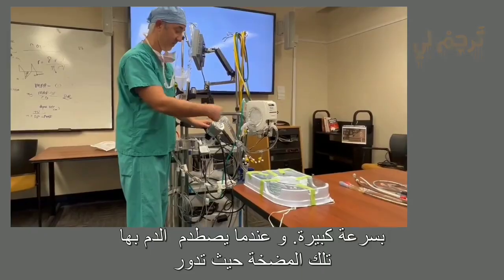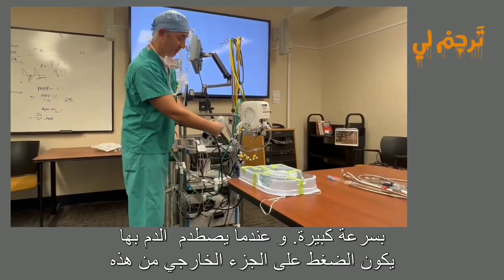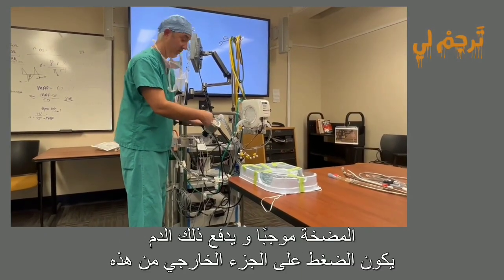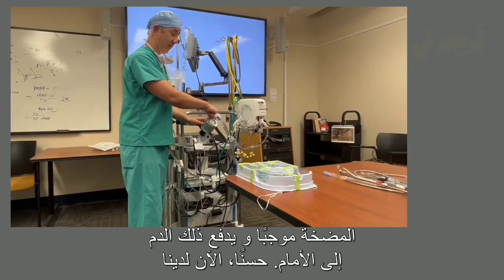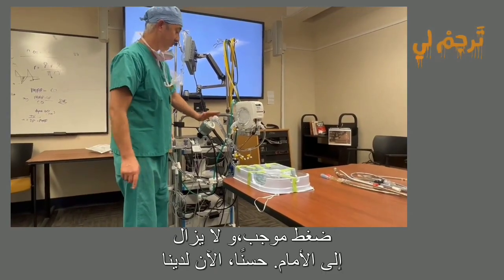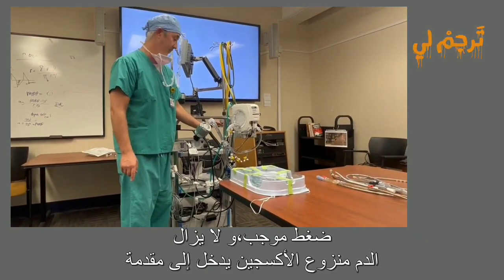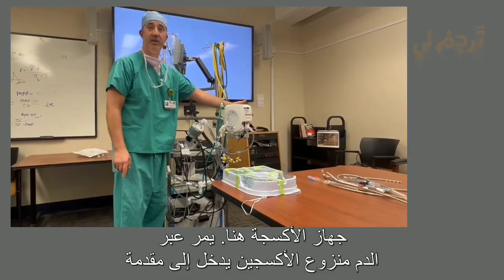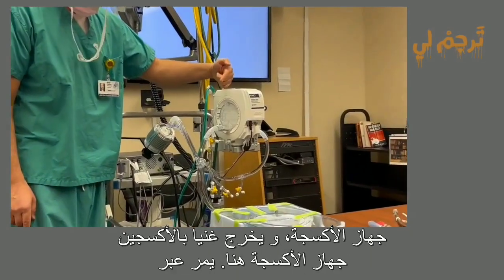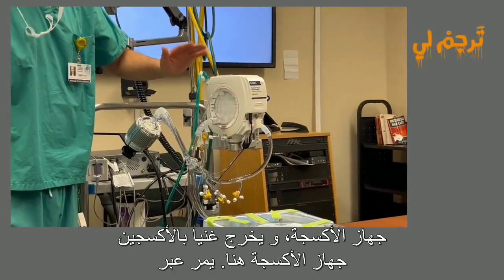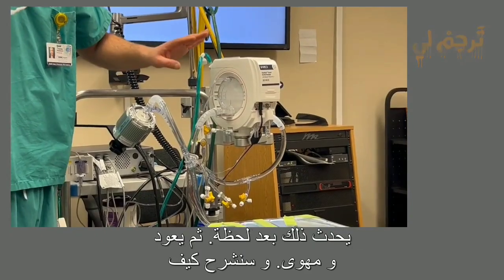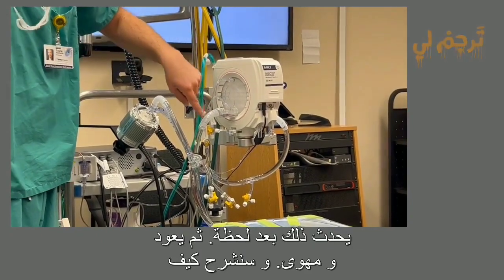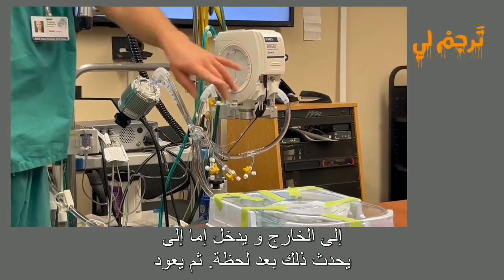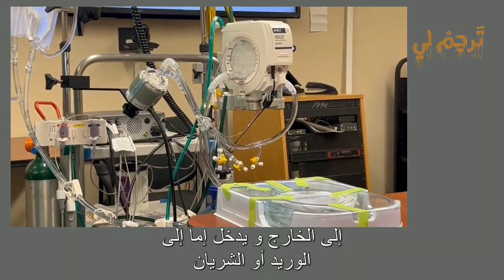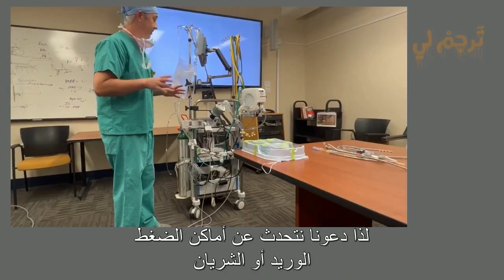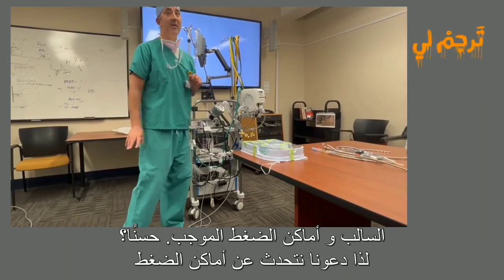where it's spinning really fast. And when the blood hits it, the pressure on the outside part of this pump is positive, and it propels that blood forward. All right, so now we have positive pressure, still venous deoxygenated blood, going into the front of the oxygenator here. It goes through the oxygenator and comes out highly oxygenated and ventilated, and we'll go over how that happens momentarily. And then it comes back out and goes back into either a vein if it's VV, or an artery if it's VA.